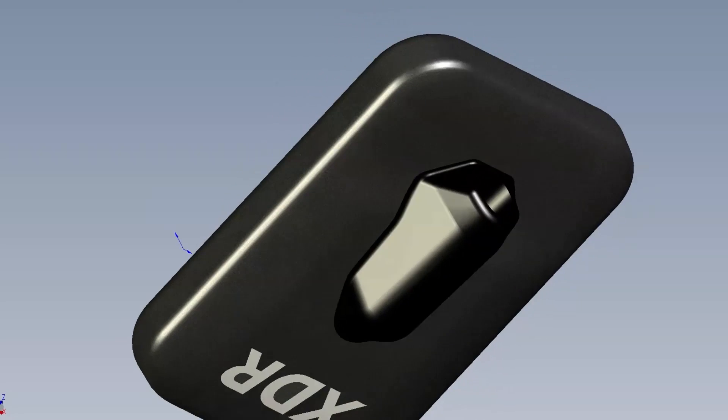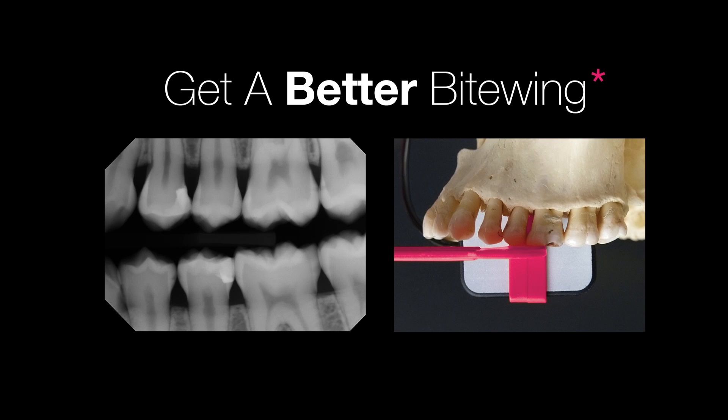Very clever. And then the other aspect is that we've minimized the dead space on the mesial side of the sensor. For historical reasons, engineers have always put the control electronics on the mesial side because it's closest to the cord. It kind of makes sense intuitively, but it really doesn't make sense clinically — because if you're trying to capture the distal of a cuspid in a bite wing, that's a problem. And anybody who's used digital knows that. When we first came out with this sensor, we heard from universities and general practicing dentists that it was much easier. Two millimeters extra imaging space — that's a huge amount.